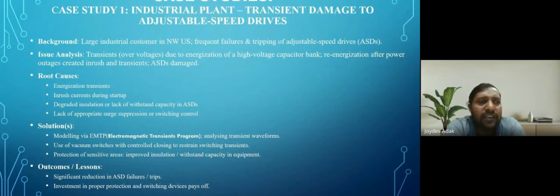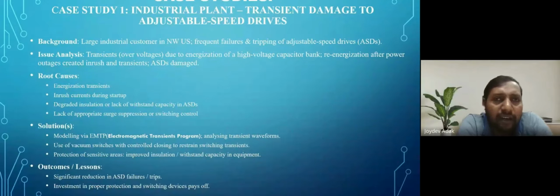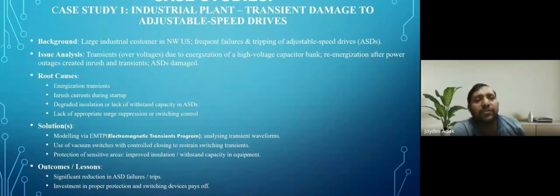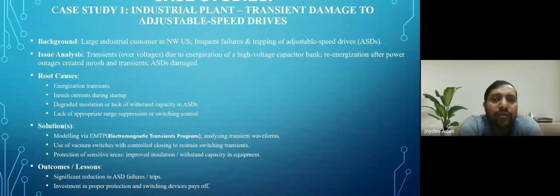So the root cause is energization transient. If the number of energizations increases, then the number of transients will increase. Due to the transient, it affects all the equipment connected to that system. The inrush current during startup is much higher. We already know that if the number of startings increases, the starting current is much higher, 5 times or 3 times the full load current. This will hamper the insulation system of the drives, and it can damage the drives after a few operations.